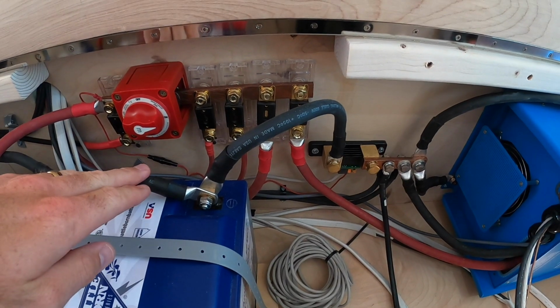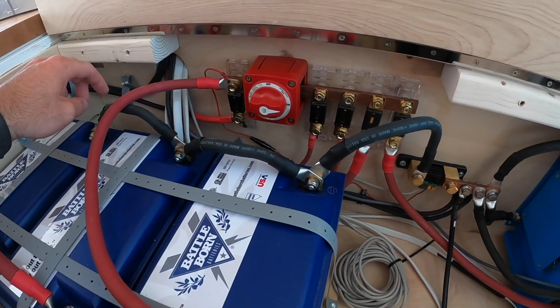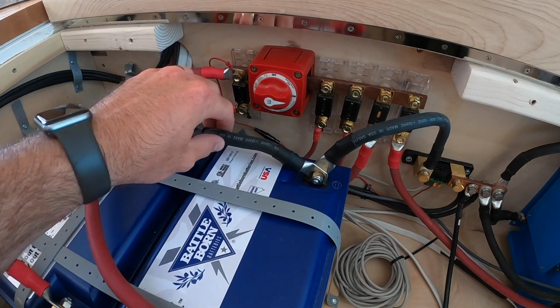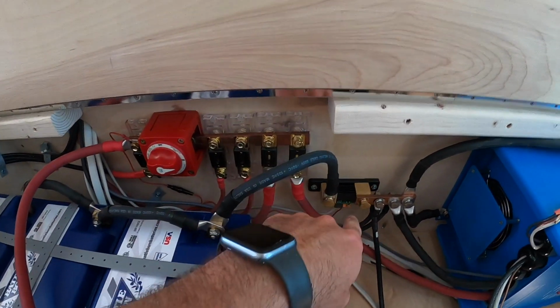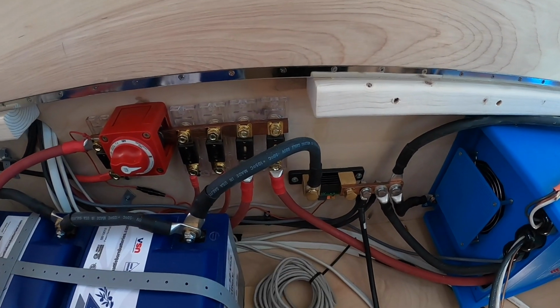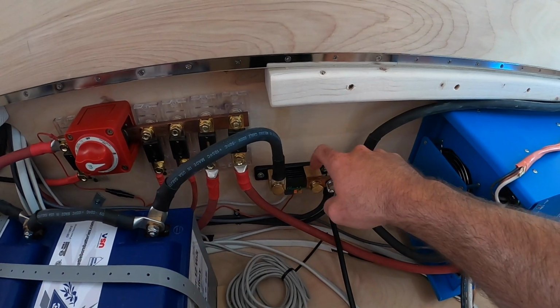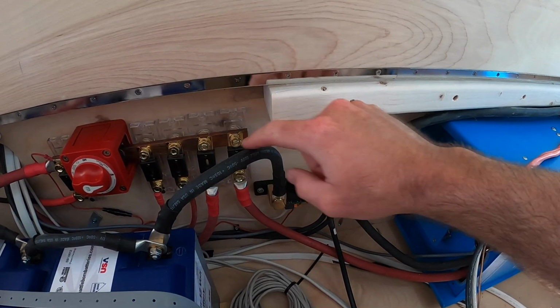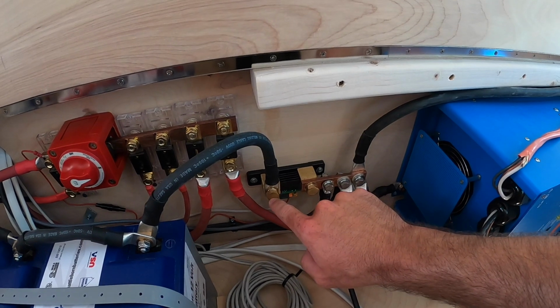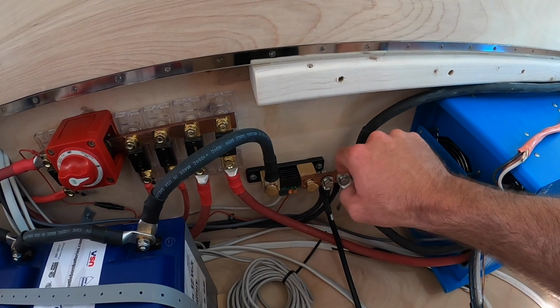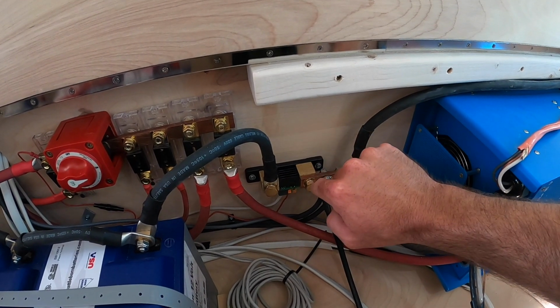Now let's take a look at the negative bus bar. Again, we have 2/0 wire coming from our batteries over to the negative bus bar, and this is where the battery shunt lives. I have this running to the battery side of the shunt, and then the bus bar on the opposite side of the shunt.